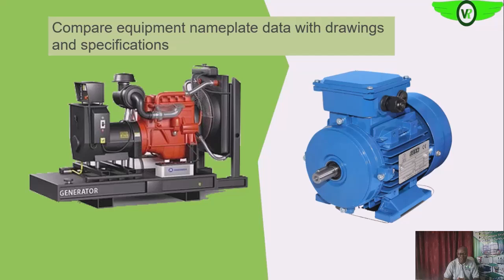physical inspection. Okay, so during the physical or mechanical inspection, what we need to do first, especially for newer units, is to look at the nameplate information of either the electric motor or the generator, to see that it actually matches the specification. Or we can also compare those nameplate information with the drawings, okay, if it is already an installed unit in our installation. So as you can see on the screen, this is the nameplate of the generator alternator.